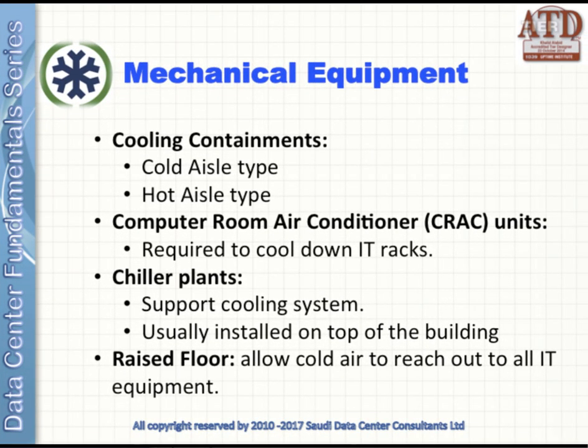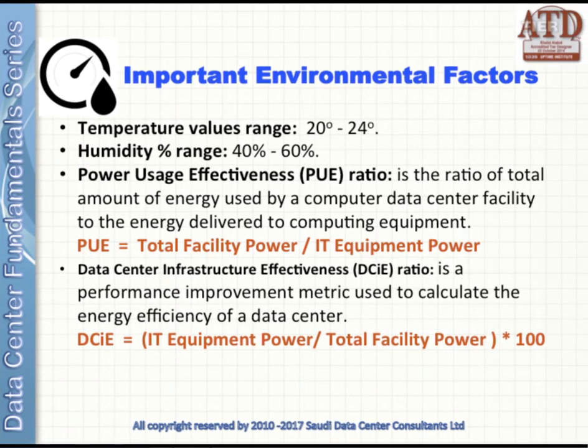The mechanical part of the data center covers the following. First, cooling containment — cold or hot aisle containment types — to provide physical separation of hot and cold aisles using blanking panels. Second, CRAC units to supply the data center with cold air. Third, chiller plants, usually located on top of the building to support CRAC units. And finally, the raised floor, which allows cold air to reach all your IT equipment.